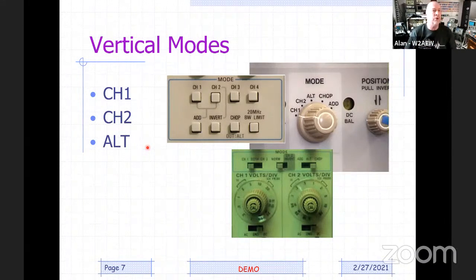There are instances, though, where you're looking at relatively low sweep speeds, like 100 milliseconds per division, which would give you one second across the screen, and you'd actually see it alternate between channel 1 and channel 2. If you wanted to look at both of those signals at the same time, the Alt mode really doesn't help you, and that's where you'd want to use something called the chop mode. What chop does is, relatively quickly, at tens of kilohertz, it bounces back and forth between coupling to channel 1 and coupling to channel 2, but you don't see that. What you'll see is essentially two beams.